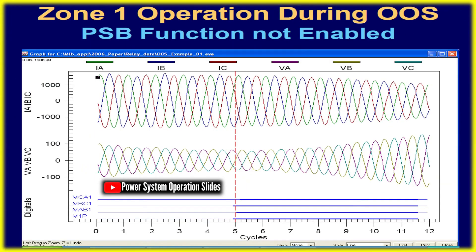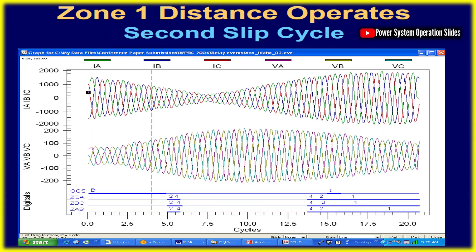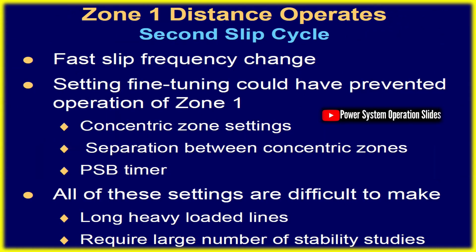Distance relays, which measure positive sequence impedance, are particularly sensitive to power swings. When an OOS event occurs, the impedance locus may enter the relay's operating region. Zone 1 elements, which operate without delay, are highly sensitive, while Zone 2 elements, used in pilot relaying schemes, are also prone to activation. Conversely, backup zones, due to their time delays, often remain unaffected by power swings.